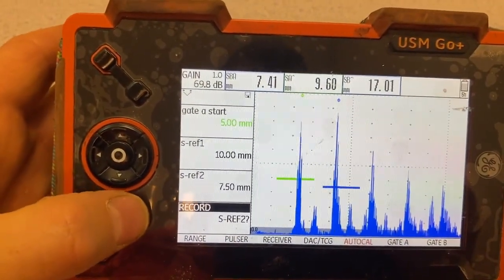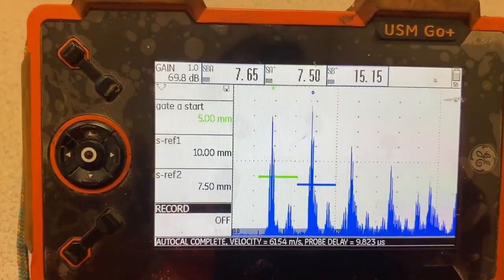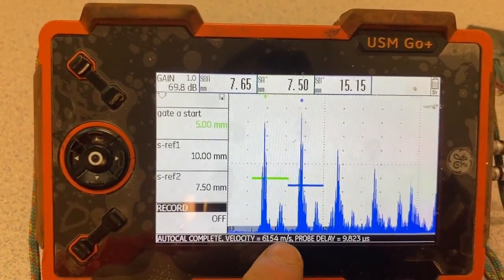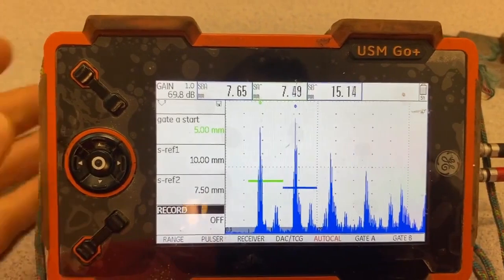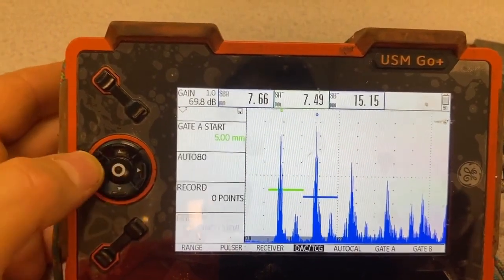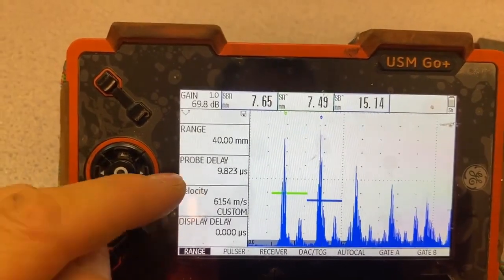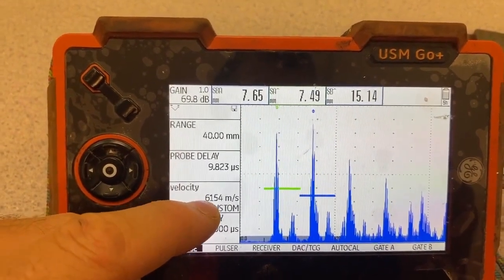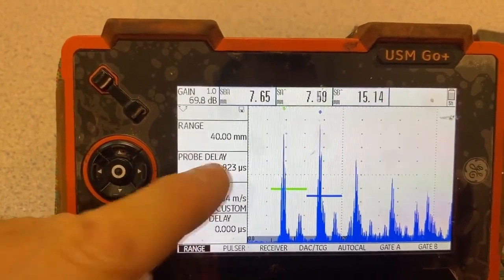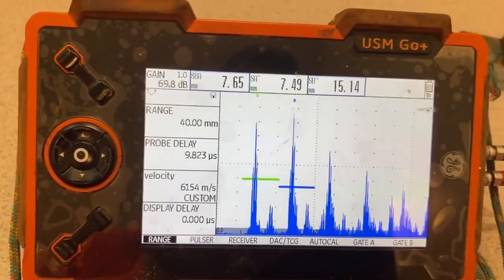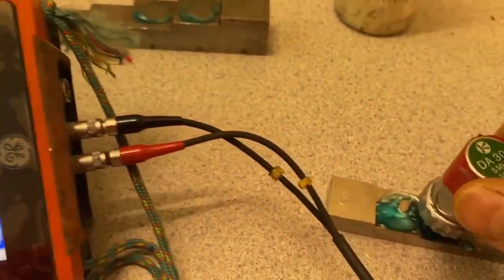Now we press record on that button, and automatically the velocity, you see the speed, and the probe delay are changed. Now we can go back to the main menu and we see the velocity is 6154 and the probe delay changed automatically. We can check what it shows. It shows on the calibration block.